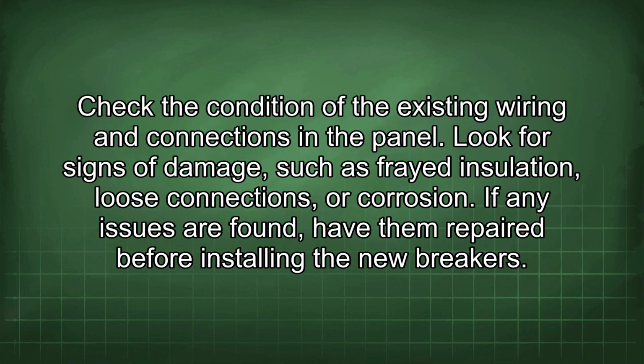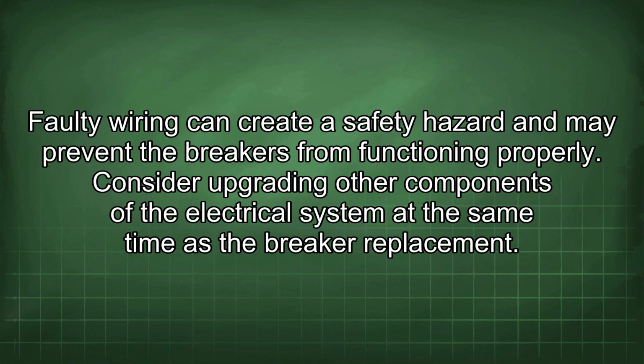Check the condition of the existing wiring and connections in the panel. Look for signs of damage such as frayed insulation, loose connections, or corrosion. If any issues are found, have them repaired before installing the new breakers. Faulty wiring can create a safety hazard and may prevent the breakers from functioning properly.